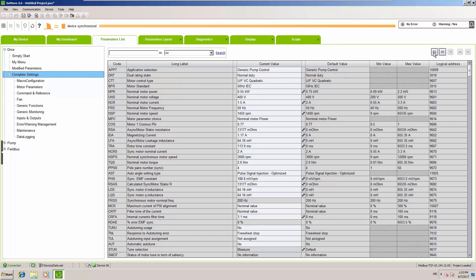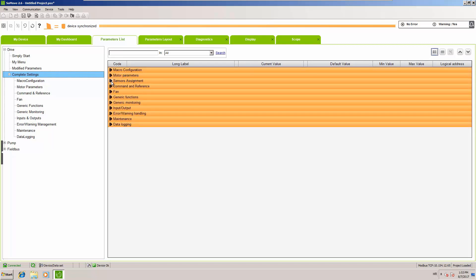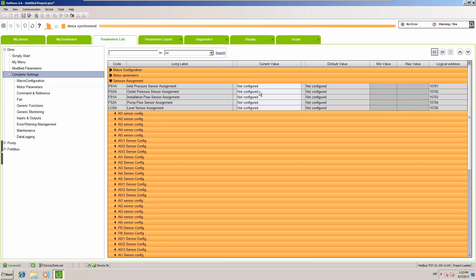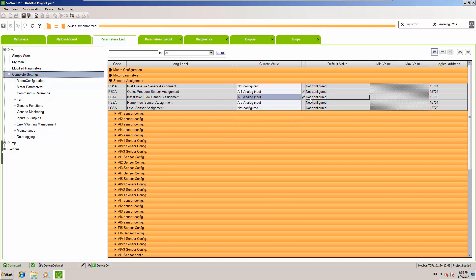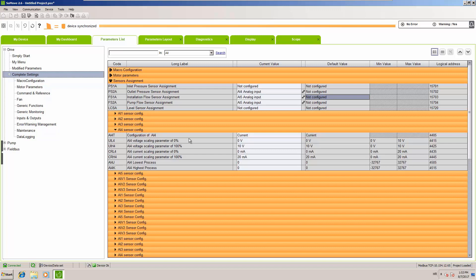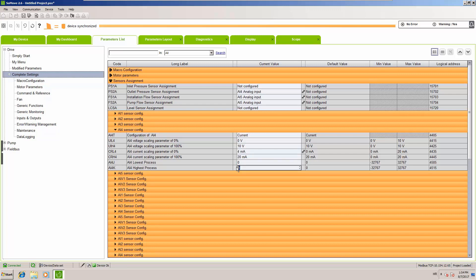Once user units are set, we can scale our sensors to the proper values. We know what values our pressure and flow meters provide according to their analog outputs — 4 to 20 mA. The outlet pressure sensor is on AI4 and the installation flow sensor is on AI5. Our sensors are 4 to 20 mA current sensors. For pressure, using 0.01 bar resolution from 0 to 2.5 bars, we set a range of 0 to 250 for correct scaling.